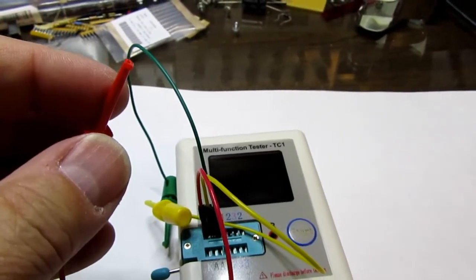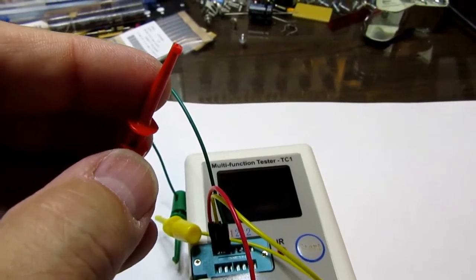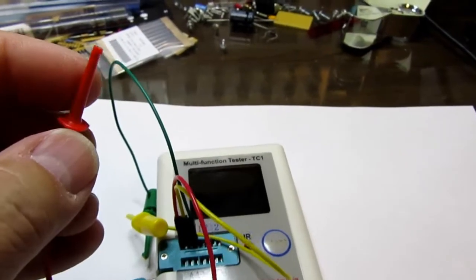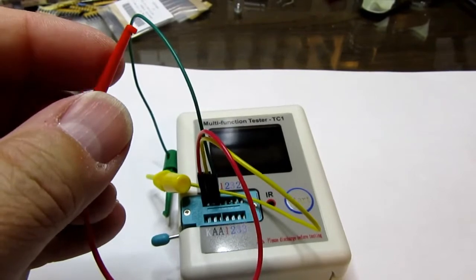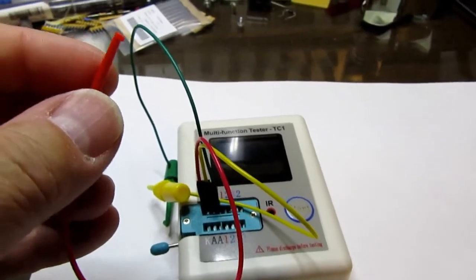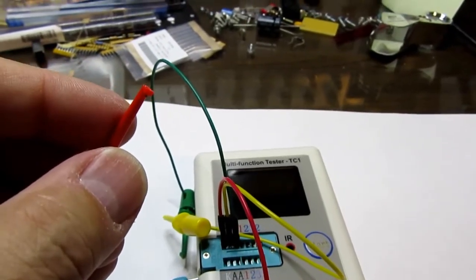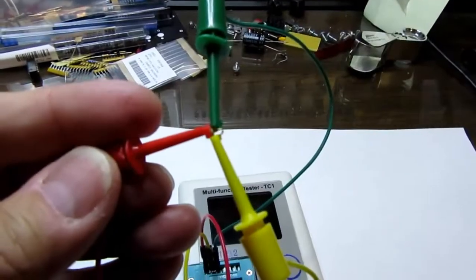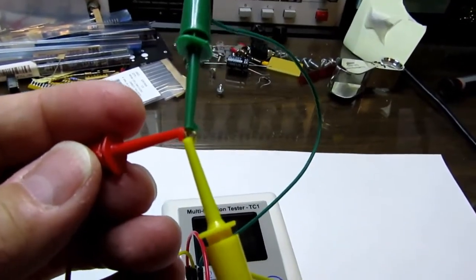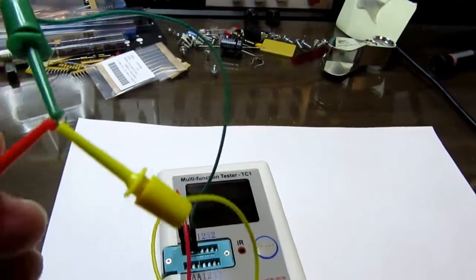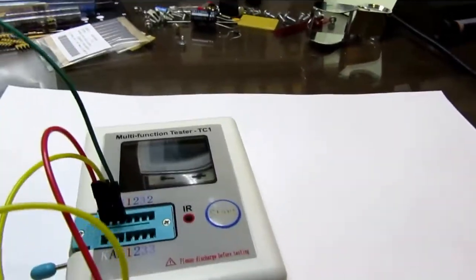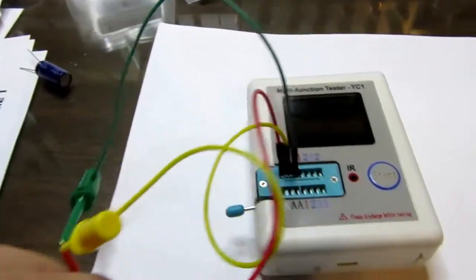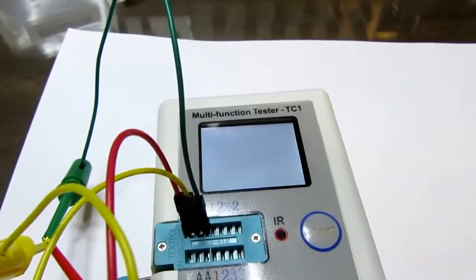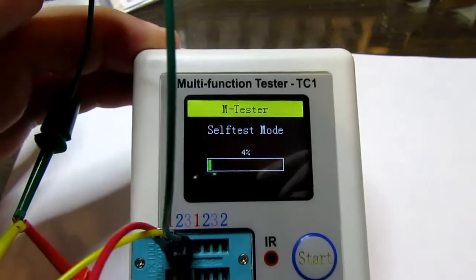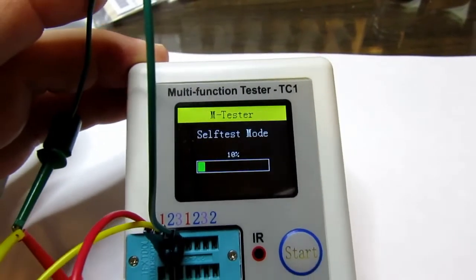They're also useful for doing a self-calibration and test. The unit does a self-power-up test every time you turn it on, but if you short all the leads together, then it does a calibration. So here I've got all 3 connectors tied together. I suppose you could just use a couple of short wire leads into the ZIF socket if you don't have these for some reason. I'm turning it on by pushing the start button, and it comes up and says it's in self-test mode.